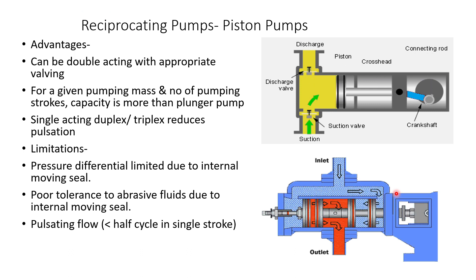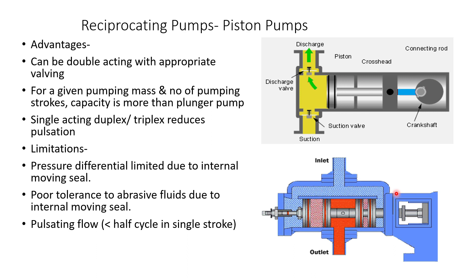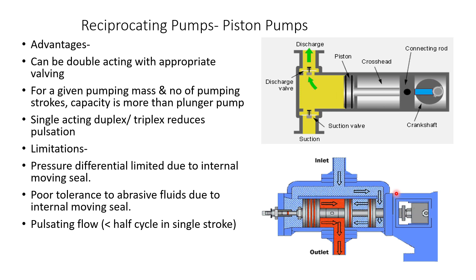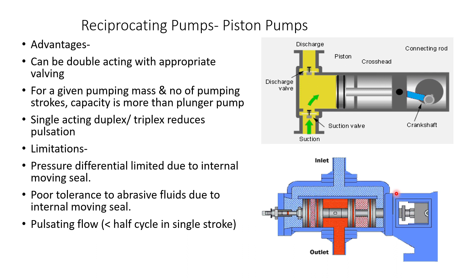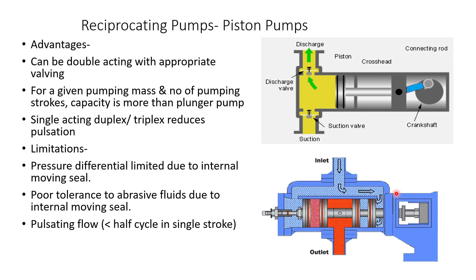Looking at the advantages of a reciprocating pump: it can be double acting with appropriate valving. For a given pumping mass and number of pumping strokes, capacity is more than a plunger pump. Single acting duplex or triplex configuration reduces pulsation. Limitations include that pressure differential is limited due to the internal moving seal — the piston seal — and it has poor tolerance to abrasive fluid. The flow is pulsating and is less than half cycle for a single stroke.